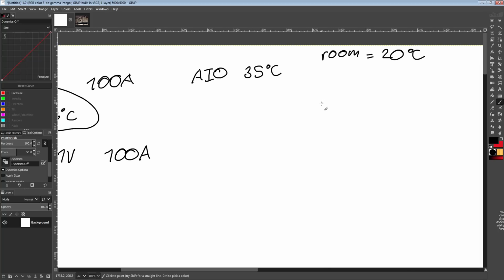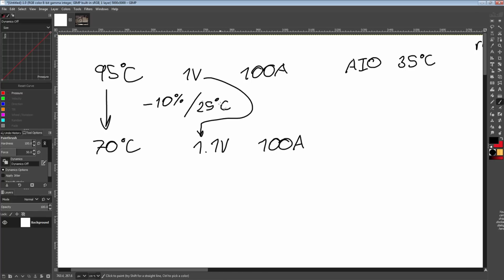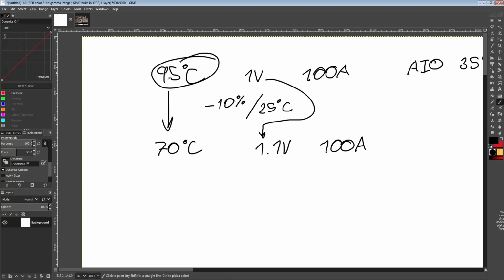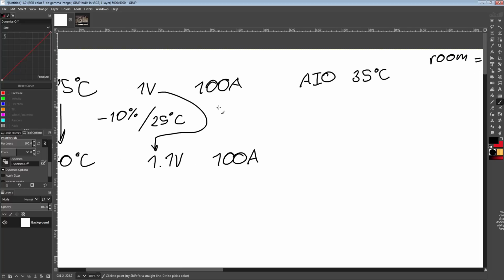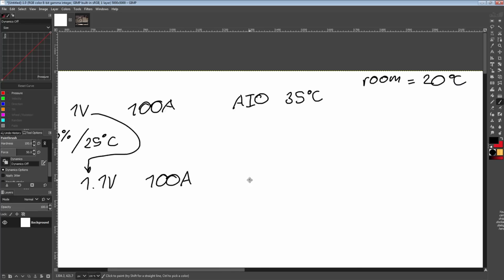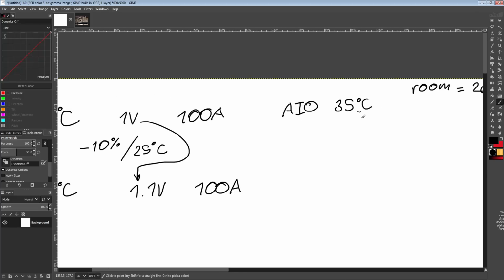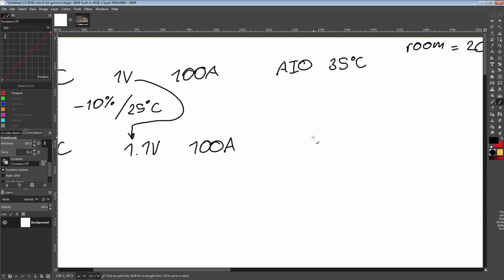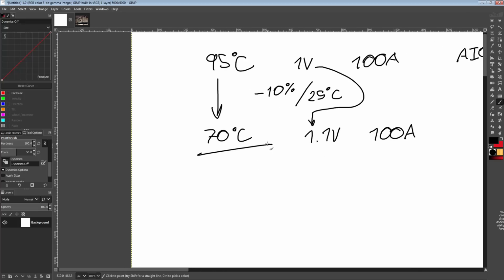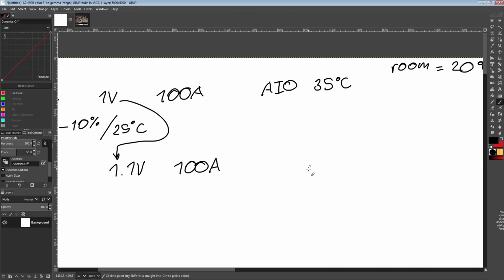Room temp equals 20 degrees, and we have a problem here. The cooling system necessary to get this lovely temperature drop is not ambient, because the AIO is at 35 degrees.